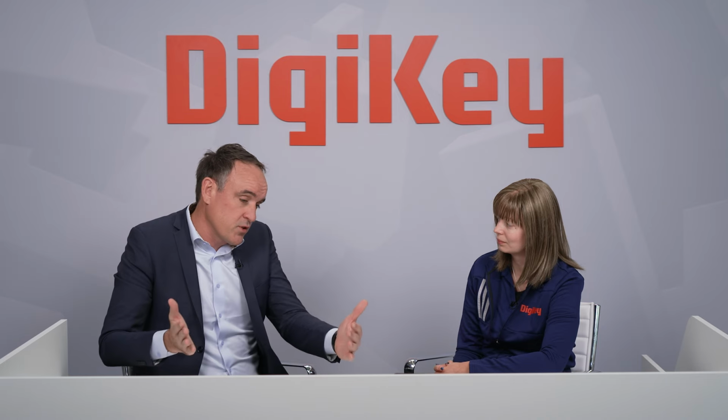Yeah, so maybe a little bit of background to the design and where we're coming from. Arc detection is an important feature in string inverter applications because it's used on rooftop solar installations in a lot of markets around the world. They require by UL standards to have an arc detector. Arc detectors have been around for a while. The current methods are fairly good at detecting arcs, but unfortunately they also detect a lot of things that are not arcs, because there are a lot of disturbances on the line that comes down from the roof into the string inverter.